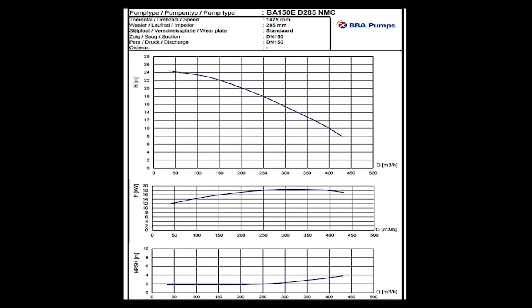This part of the pump curve shows the required suction head. If the pressure is above this line, you are okay, and if it is below it, the pump will cavitate. The required minimum pressure is shown in absolute pressure.